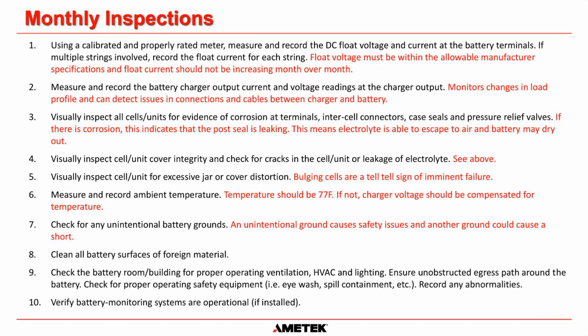What that does is it allows people to work on the battery safely, because obviously they're leaning across the rack, which is made of metal. Yes, it's usually covered in a plastic epoxy resin of some sort and is insulated, but there are going to be some breaks in that insulation. So if somebody is leaning across a battery rack and his or her arm touches metal on the rack and then touches a battery post, you should not be exposed to a shock. If it's floating, you will not be exposed to a shock. But if there is a ground on the battery, whether accidental or not, that poses hazards for people working on the battery and could allow them to get a shock.